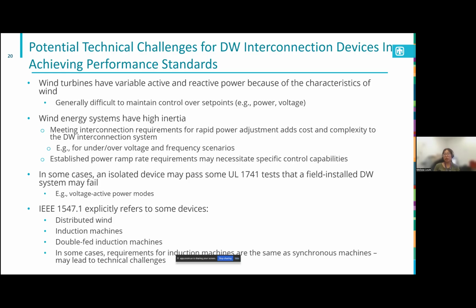In addition, the high inertia of wind energy systems may necessitate more costly and/or complex controls to meet requirements such as those regarding rapid power adjustment in out-of-range voltage or frequency scenarios. Similarly, power ramp rate requirements may also require specific and complex control capabilities.